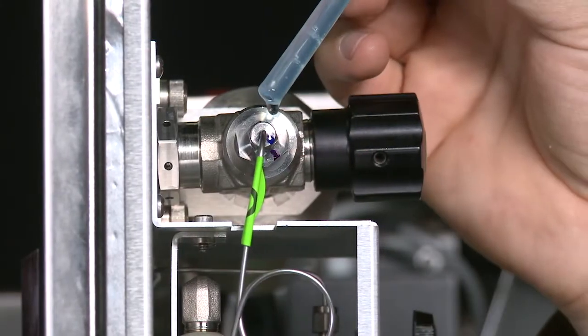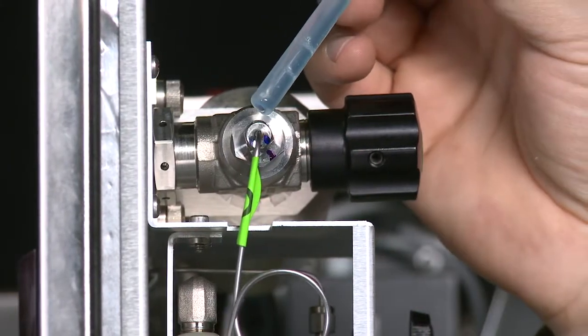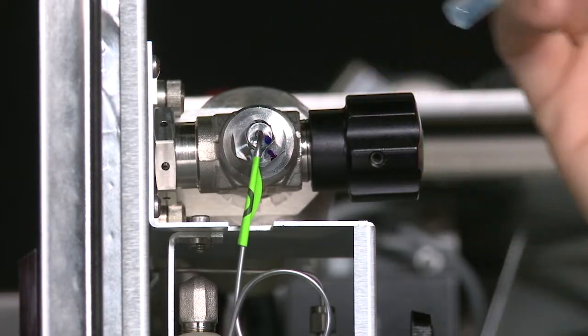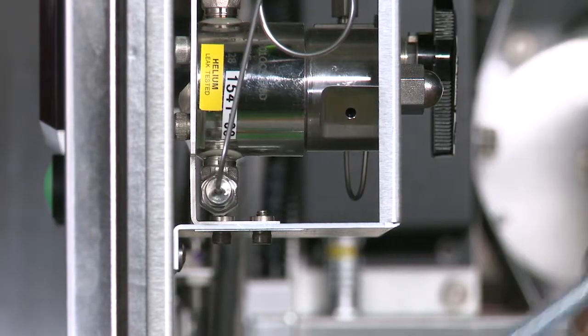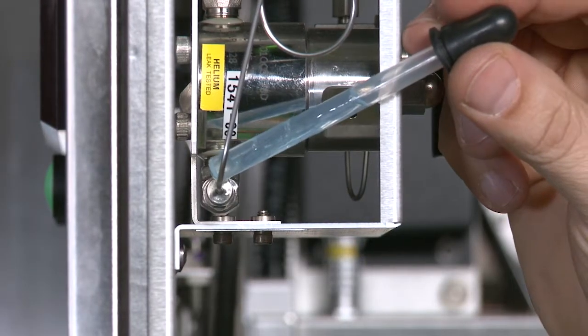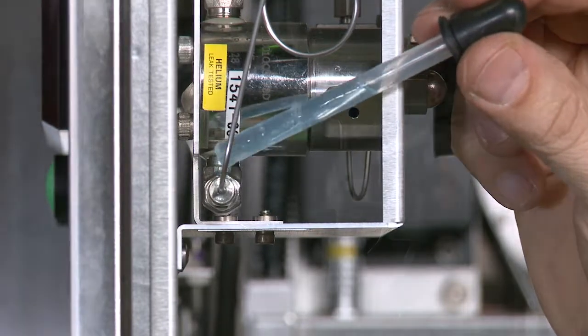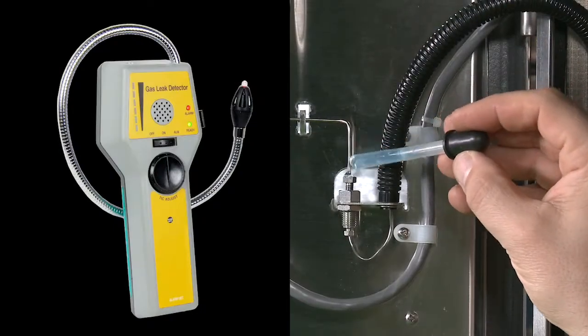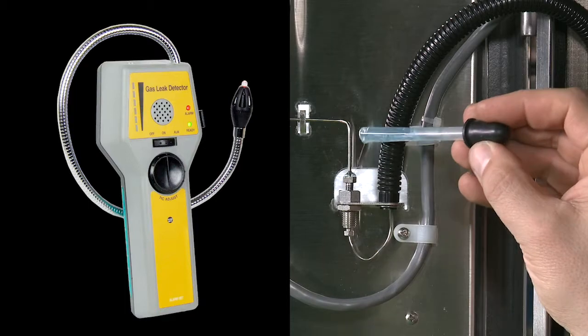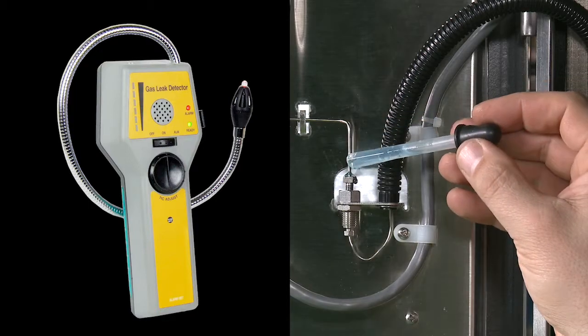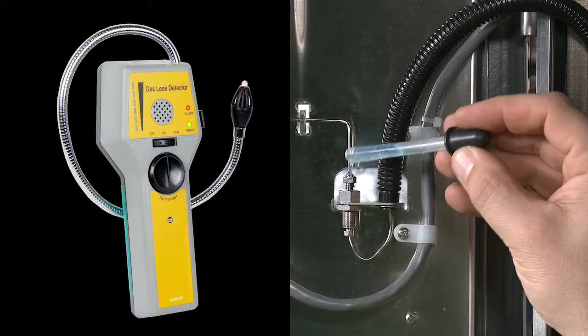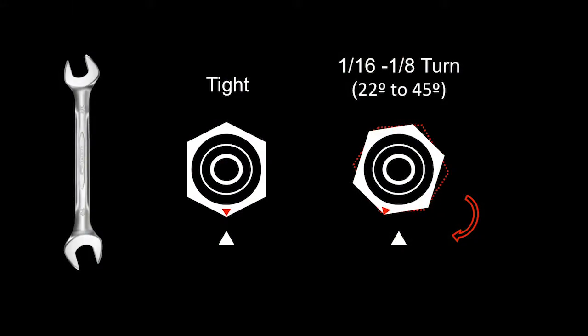If a leak-checking fluid such as Snoop or Cal Blue is available, it is recommended to check the accessible fittings, particularly those that have been connected in the field. A portable helium leak detector may alternatively be used to sniff for leaks around the fittings on a wind-still day. If a leak is detected, tighten the leaking fitting by 1/16 to 1/8 of a turn. If the leak persists, contact Morgan Schaffer.